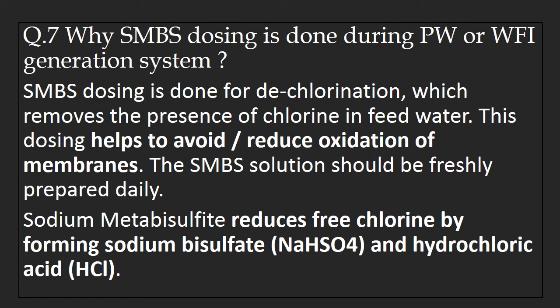Question number 7: Why is SMBS dosing done during purified water or WFI generation? SMBS dosing is done for dechlorination, which removes the presence of chlorine in feed water. This dosing helps to avoid or reduce oxidation of membranes. The SMBS solution should be freshly prepared before use, as sodium metabisulphite is readily oxidized when it comes in contact with air. Sodium metabisulphite reduces free chlorine by forming sodium bisulphate and hydrochloric acid.